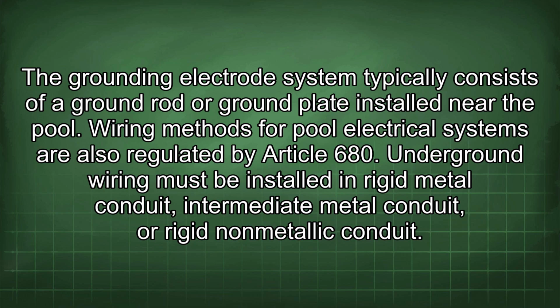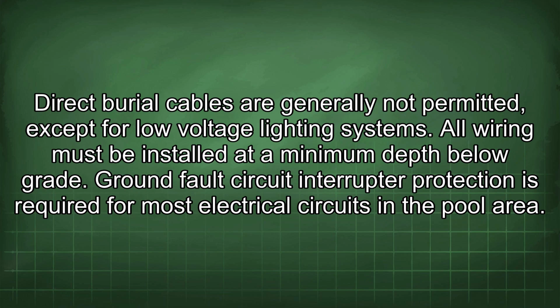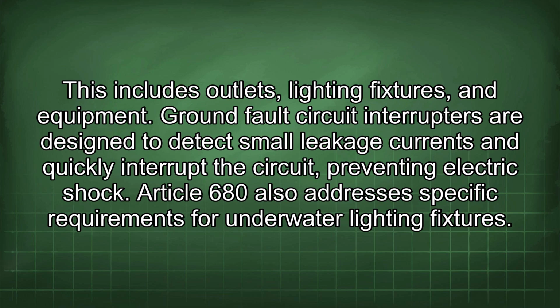Wiring methods for pool electrical systems are also regulated by Article 680. Underground wiring must be installed in rigid metal conduit, intermediate metal conduit, or rigid non-metallic conduit. Direct burial cables are generally not permitted, except for low-voltage lighting systems. All wiring must be installed at a minimum depth below grade. Ground fault circuit interrupter protection is required for most electrical circuits in the pool area. This includes outlets, lighting fixtures, and equipment.